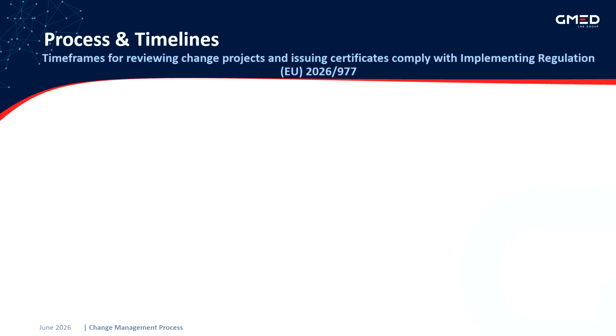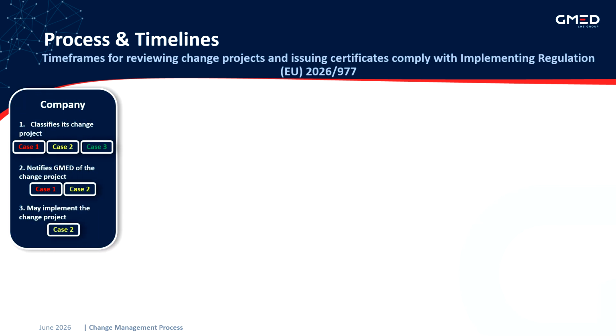Depending on the category of the change project, one or more steps in the change management process must be completed. The first step involves the company categorizing the change project. If the company determines that the change project falls under Case 3, no notification to GMED is required. If the proposed change falls under Case 2 or Case 1, the company must notify GMED.